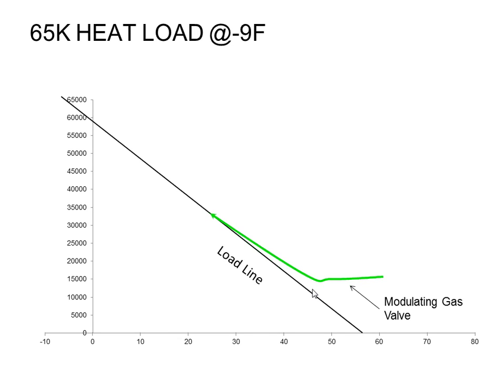And then it'll go ahead and kick on and maintain 65 continuously until the next morning. Then it'll ramp up again. So that's kind of the story about this furnace, is it basically never shuts off. Like I said, you might have homeowners that perceive that to be an energy-consuming problem, but it actually ends up saving a little bit of energy because you have more even temperatures throughout your house, so you don't try to overcompensate with a different set point. And you're still buying the same amount of therms basically from the gas company.